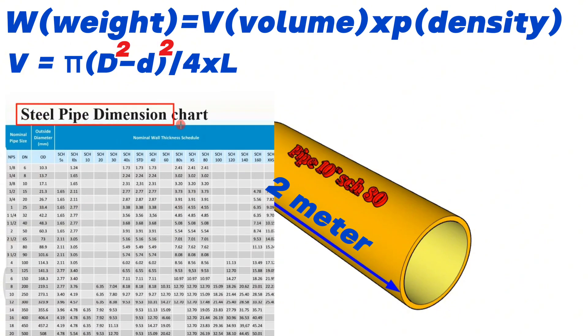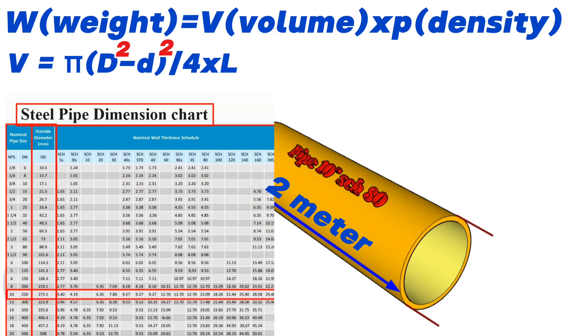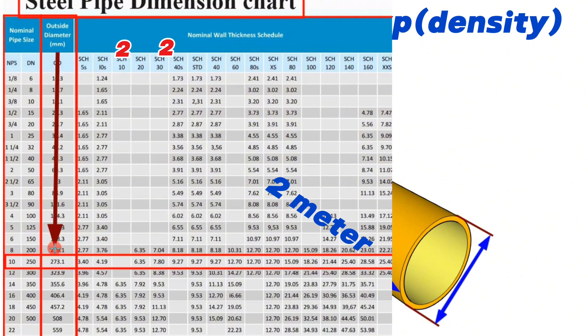This is the steel pipe dimension chart. The nominal pipe size is shown in the first column. The outside diameter of pipes is shown in the second column. The nominal wall thickness schedule is shown in the last column. Looking at the row for nominal pipe size 10 inch, the outside diameter is approximately 273 millimeters and the wall thickness for schedule 80 is 15.09 millimeters.